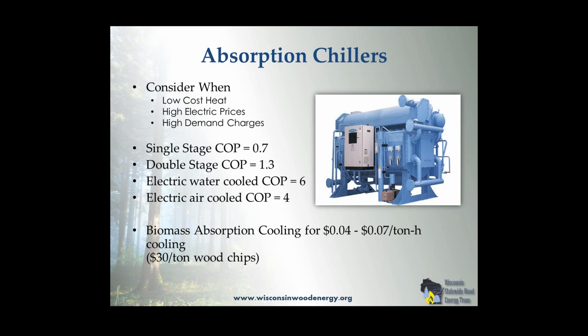So if I have to put in 1 million BTUs to get 700,000 BTUs of cooling, that doesn't sound too bad, unless you look at electric-driven systems. Generally on systems the size that these are, in the 100 horsepower or 100 ton or bigger, the coefficient of performance for these centrifugal systems is in the range of 5 to 1. In other words, for 1 unit of electric I put in, I get 5 units of cooling out. So when you compare absorption chillers to conventional centrifugal chillers, it's a little bit tough to compete. You have to have really big advantages in energy costs to make them stand on their own. But there are cases and places where they do work and can be very effective.